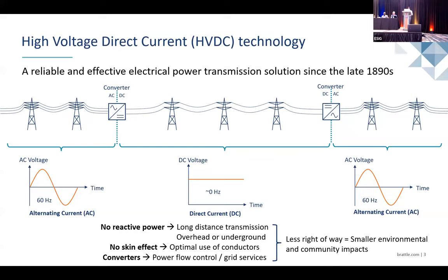The main point is that DC is zero frequency. And because of the zero frequency, you get a lot of advantages. Firstly, when there is no frequency, you don't have a magnetic field. When there is no magnetic field, there is no flux linkage. When there is no flux linkage, there is no reactance. When there is no reactance, there is no reactive power. When there is no reactive power, you can utilize the line very efficiently. That means basically we can make the conductor thinner compared to the AC system, and you can optimize it. At the same time, in AC you are sending power over three conductors. In DC, you're sending the power over two conductors. That means your right of way for a transmission line corridor is small.